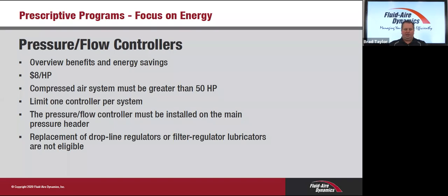Yeah, so I think the answer may be in our last point there. The difference between flow controllers and regulators is flow controllers have a very low pressure drop across them. You usually have some type of electronic sensing device with a motorized butterfly valve internal to them. So the pressure differential when wide open is less than 1/2 PSI. The reason that regulators are not incentivized is because there's a pressure drop that escalates very quickly across the curve as the flow through the regulator increases.